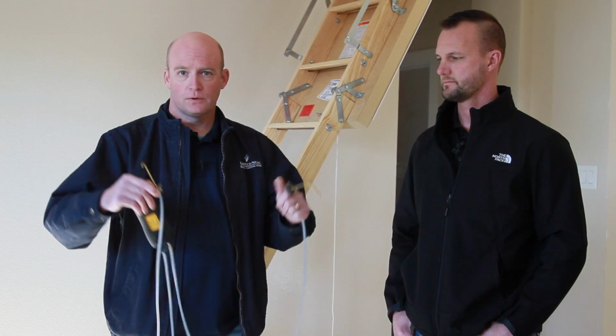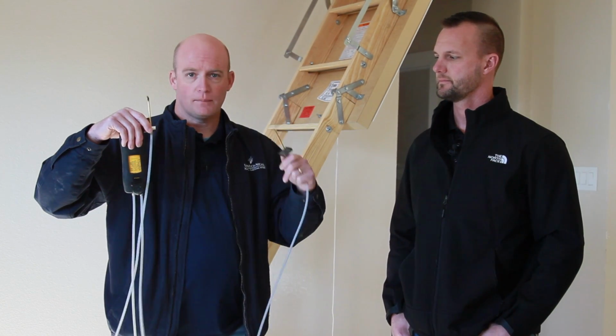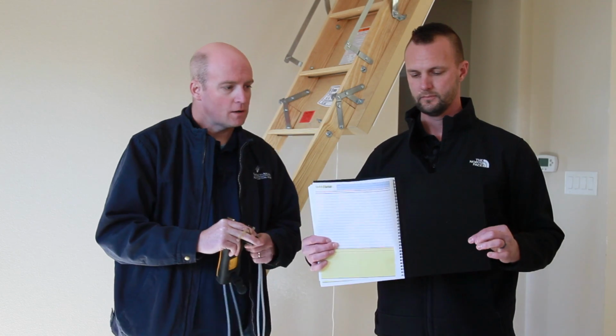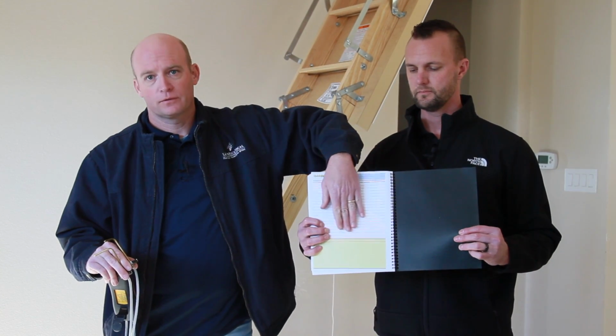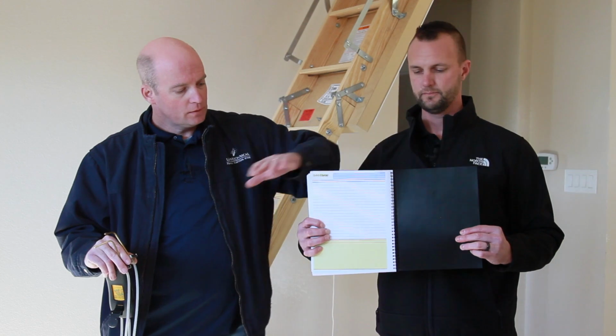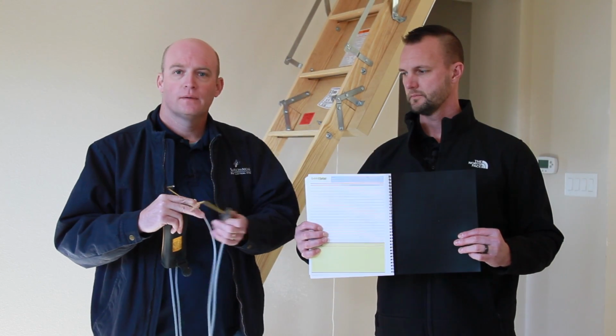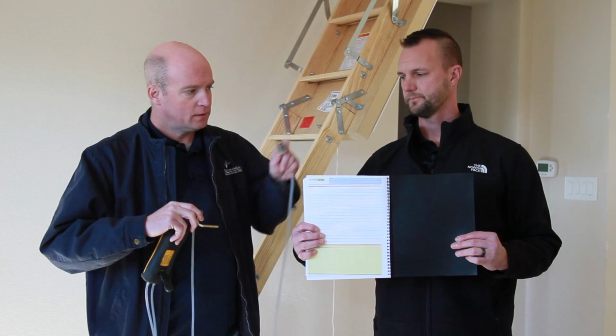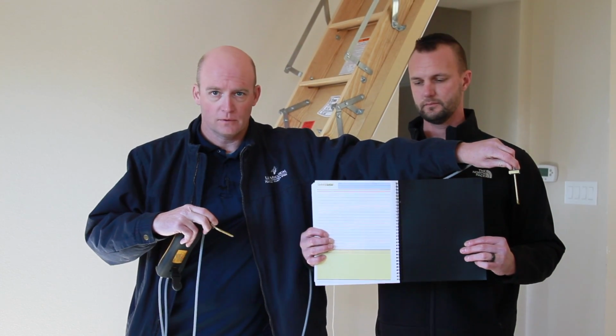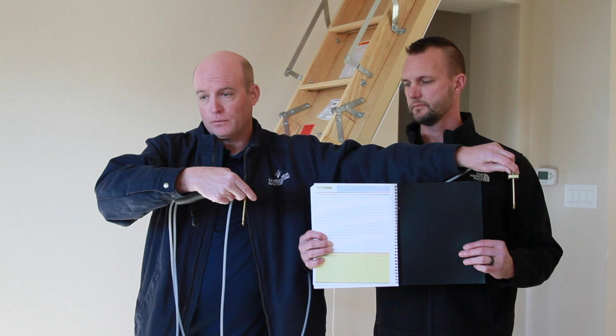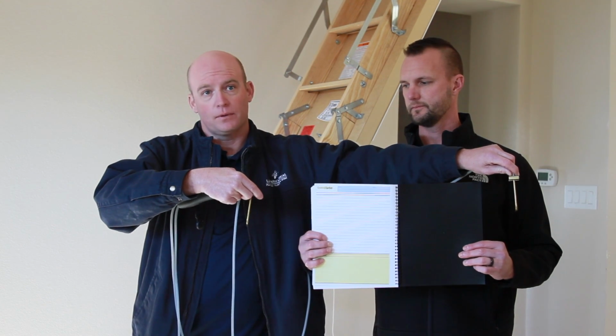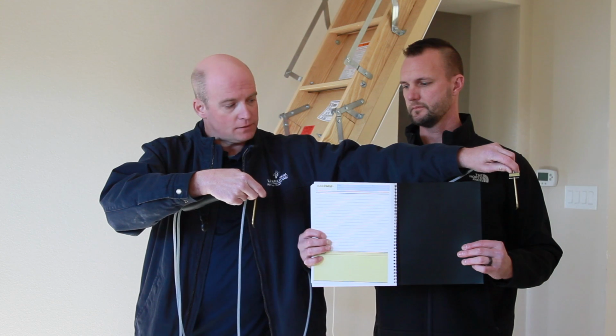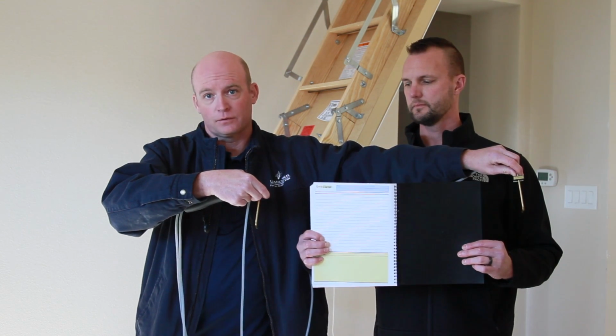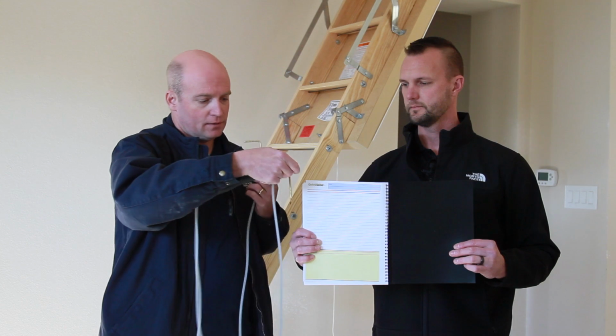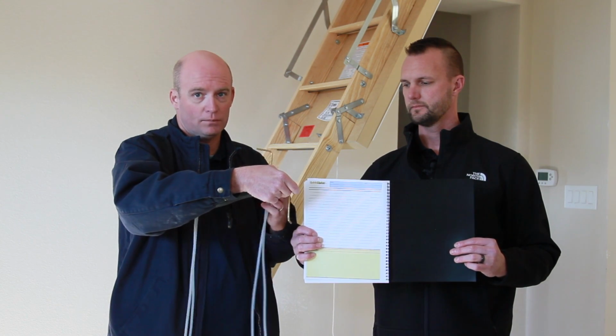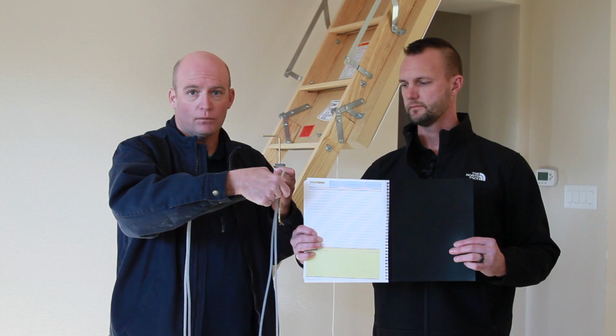There are two probes. One of the first things I want to talk about is location. For our example, this is going to be our furnace. This is our coil. We'd have a plenum here and a plenum here. Myth number one I want to talk about, everybody thinks the static pressure probe goes in the plenum and the other plenum. That will give us a reading. It will tell us our pressure drop across the entire system. It will not tell us anything about the CFM going through that furnace. The reading has to be taken closer to the furnace. It can still be in the plenum or, if you take the filter out, that'll suffice.